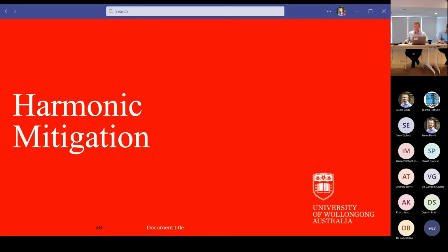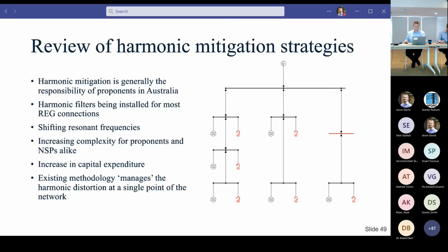Okay, so this is, fairly certain, the final section that I'll be presenting on, and it has to do with harmonic mitigation. Zooming out a little and looking at a simple network as a whole, the fundamental philosophy of the IEC harmonic management methodology, in networks with sufficiently long feeders or in highly meshed transmission networks, is to manage the harmonic voltage distortion levels at a particular point in the network. Because there is such variation of harmonic impedance across long feeders, we can show that your network will not reach your planning levels in a uniform manner.